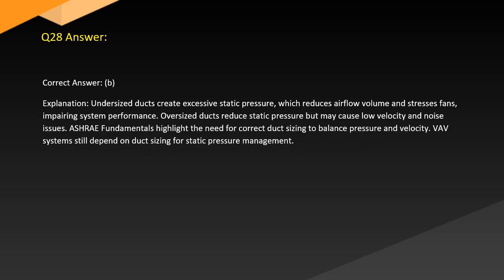Answer. Correct answer: B. Explanation. Undersized ducts create excessive static pressure, which reduces airflow volume and stresses fans, impairing system performance. Oversized ducts reduce static pressure but may cause low velocity and noise issues. ASHRAE fundamentals highlight the need for correct duct sizing to balance pressure and velocity. VAV systems still depend on duct sizing for static pressure management.